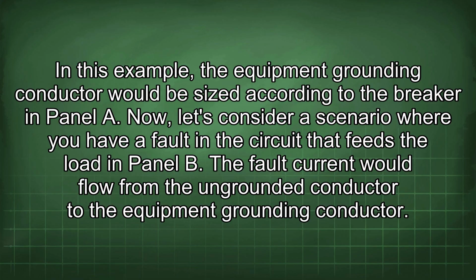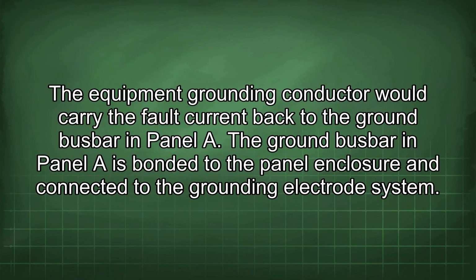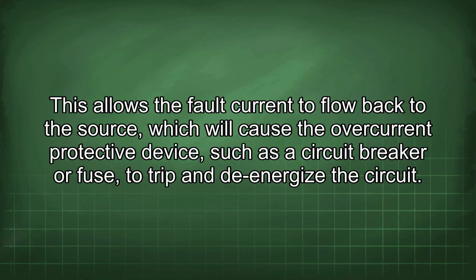Now, let's consider a scenario where you have a fault in the circuit that feeds the load in Panel B. The fault current would flow from the ungrounded conductor to the equipment grounding conductor. The equipment grounding conductor would carry the fault current back to the ground busbar in Panel A. The ground busbar in Panel A is bonded to the panel enclosure and connected to the grounding electrode system. This allows the fault current to flow back to the source, which will cause the overcurrent protective device, such as the circuit breaker or fuse, to trip and de-energize the circuit.